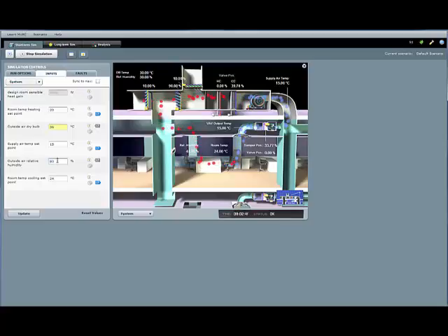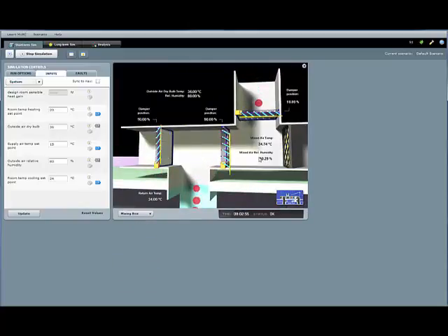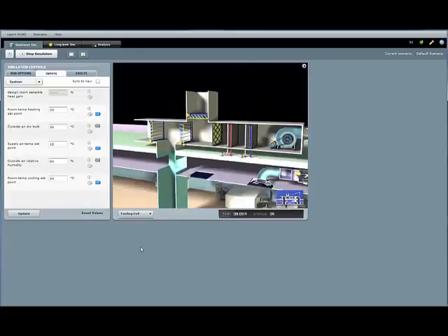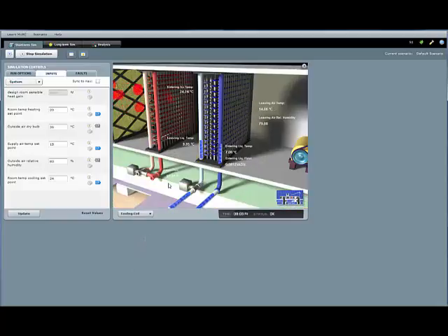Now we're increasing the temperature of the outside air and the humidity, and we'll see that the major impact of this is that the cooling coil now has its valve position open almost to 100%. This is about the limit of what this system can handle. So the cooling coil is at 100% at that point. Here we see the dampers are still 10% open for outside air, and you see we're still maintaining the cooling set point of the system.